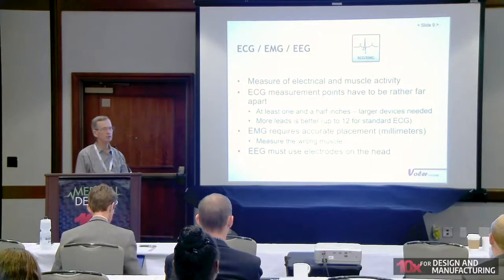EMG measures the same sort of electrical signal but on muscles. A very common place is on the forearm — you can detect individual muscles and determine which finger is moving from an EMG signal. However, there's a limitation: if you're off by a few millimeters you're on the wrong muscle and detecting the wrong finger. Positioning something accurately within one or two millimeters on the wrist is a real challenge. For EEG, measuring brain signals, the only place you can do it is on the head — forehead, temples — and there are helmets that do these measurements.